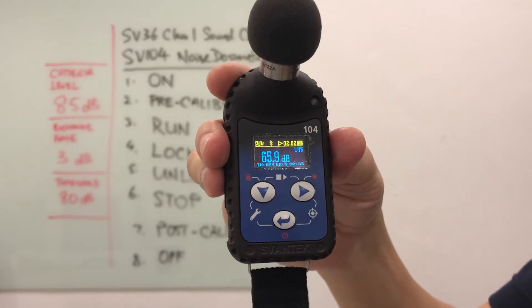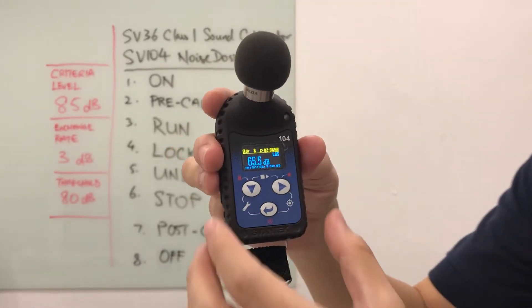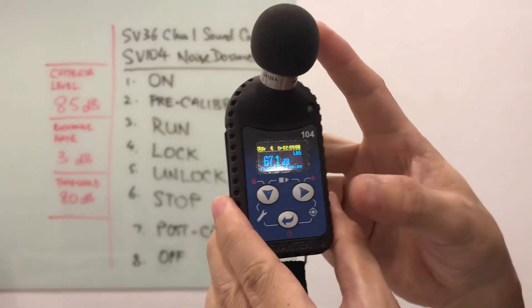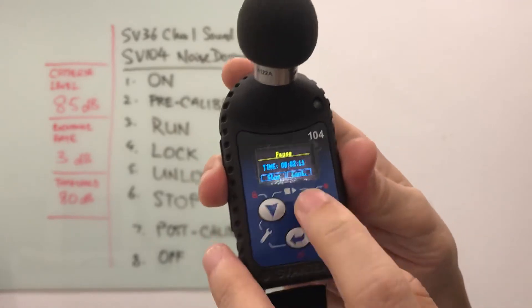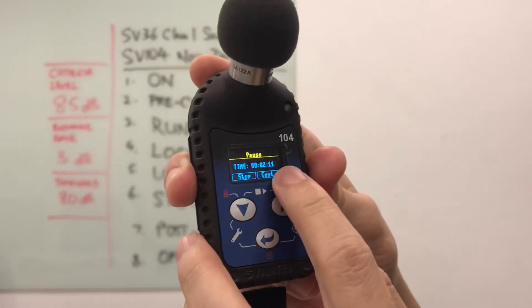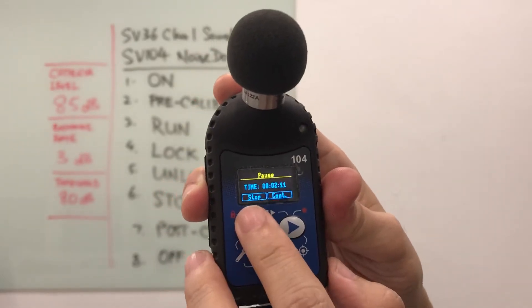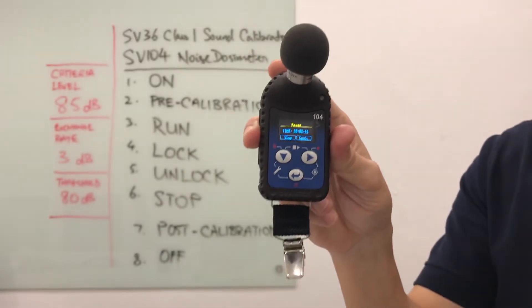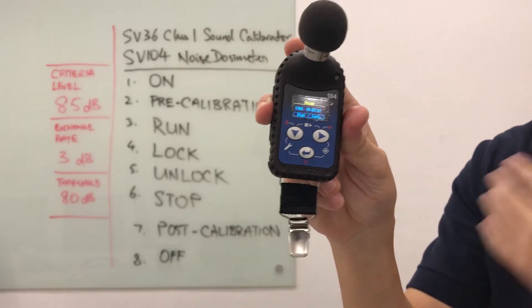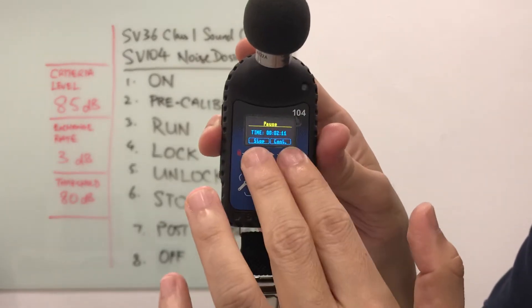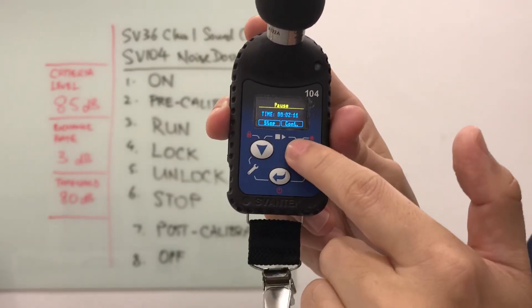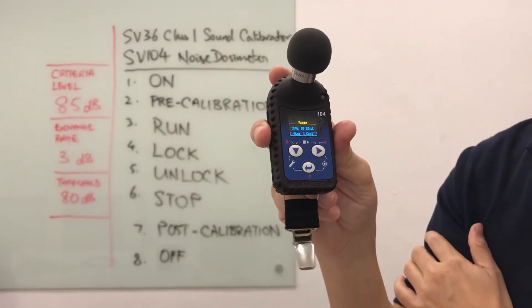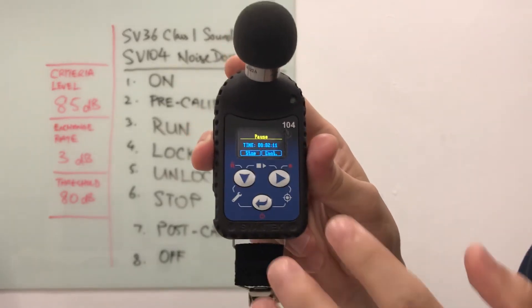At this stage, let's say I want to stop the recording. The square button and the triangle button over here, press these two buttons together. We see that the device has been put into a pause mode. The runtime is about 2 minutes and 11 seconds. Either I stop it right now or I continue. If for whatever reasons I need to pause the recording in the middle of the monitoring, this is what I'll do. I would press these two buttons and it will go into a pause mode. If I want to continue, I press this button to restart the monitoring.